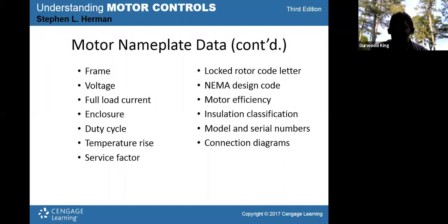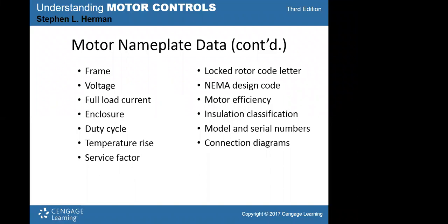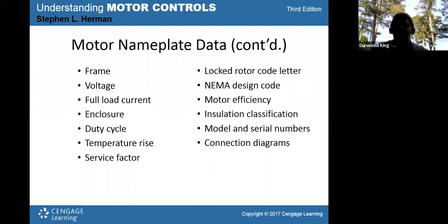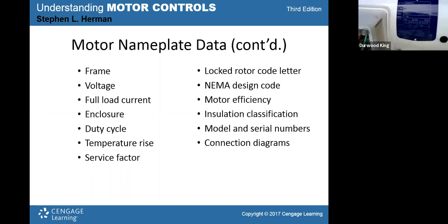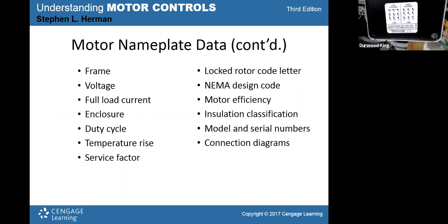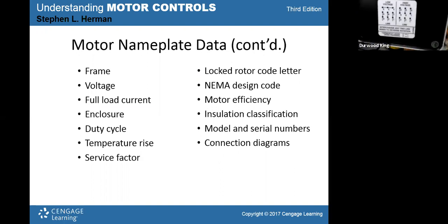Okay, so that motor data plate is on all your motors. It also has the frame size on there, and we're going to look at that. The voltage, full load current, enclosure type, duty cycle, temperature rise, service factor, locked rotor code letter, NEMA design code, efficiency, insulation classification, model, serial number, and connection diagrams. That's a lot of information, but seriously, when you take a glimpse at that motor, everything that I just mentioned is all right there. And your connection diagram is right there inside the cap head, what we call the cap head, where your wires are.